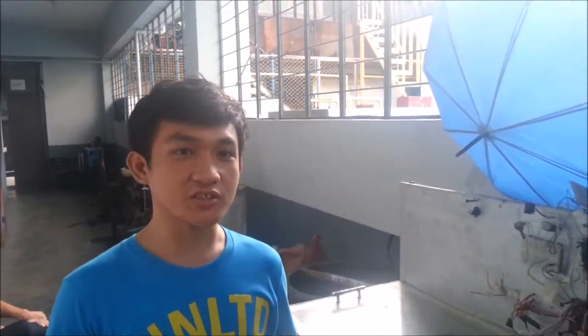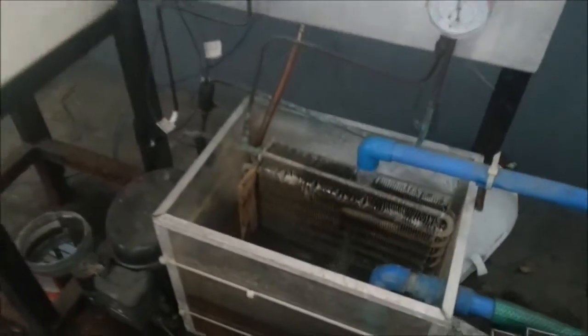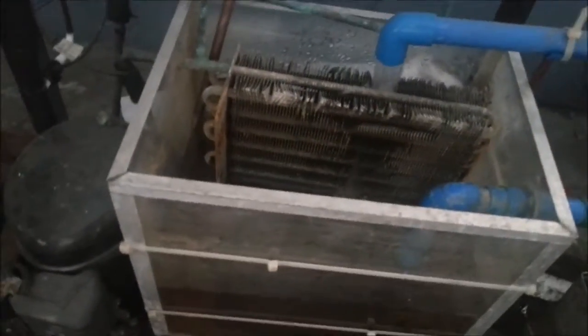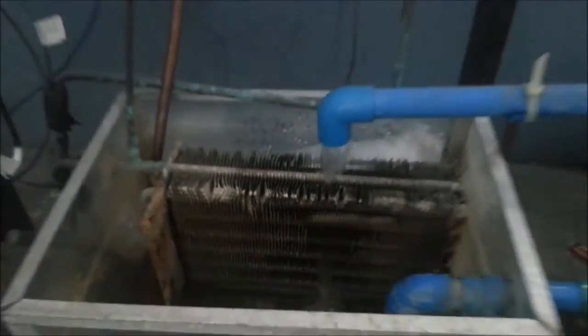The different functions. First, the compressor. It is used to compress the vapor refrigerant from the evaporator and to raise its pressure so that the corresponding saturation temperature is higher than that of the cooling medium. Second, the condenser. It is an important device used in the high pressure side of a refrigeration system. Its function is to remove heat of a hot vapor refrigerant discharged from the compressor.